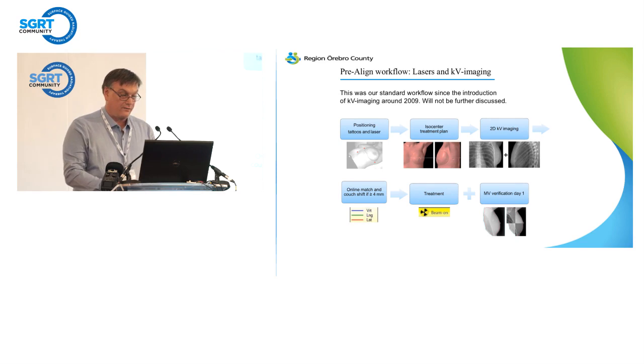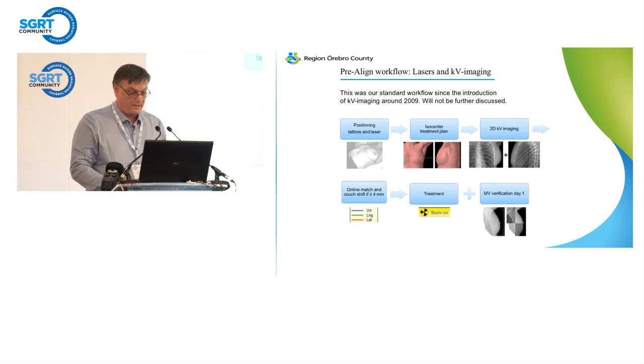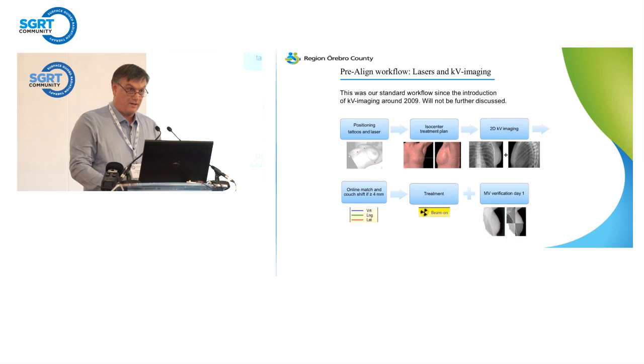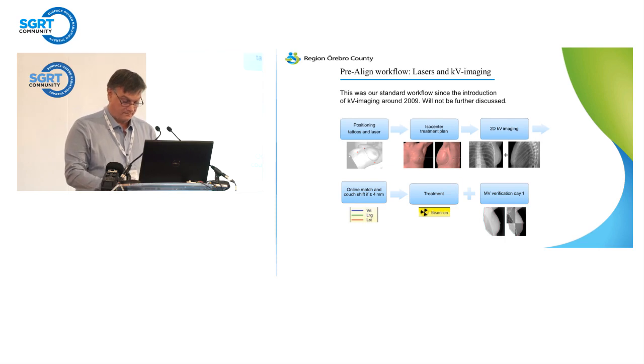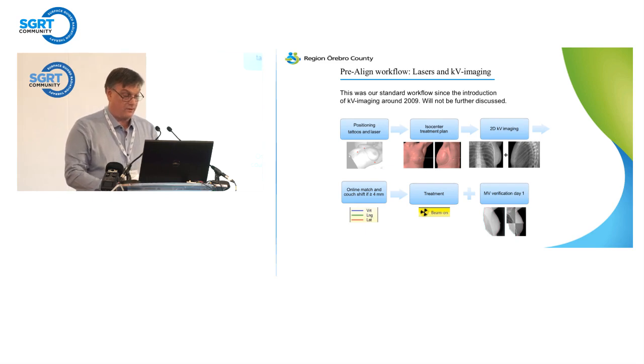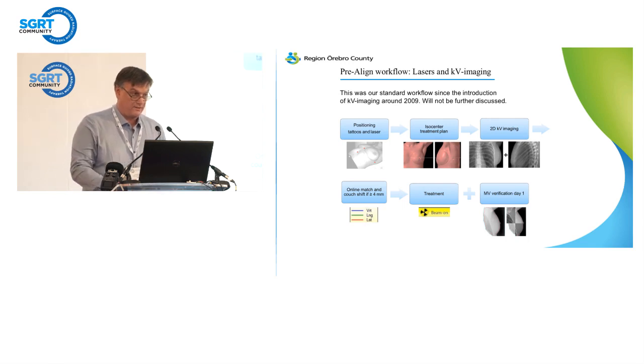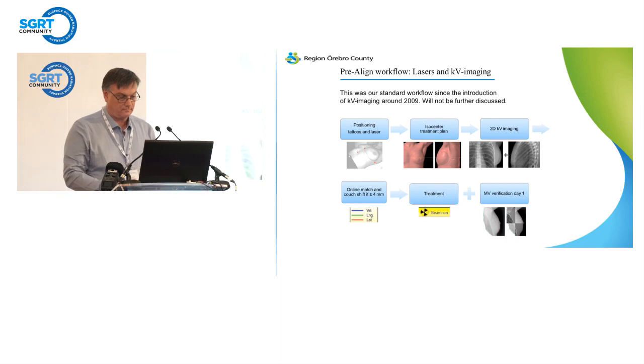This is our pre-AlignRT workflow — quite standard procedures at the time. We set patients up according to lasers, we do 2D KV imaging, we do an online match of the KV imaging, we do treatment and MV verification at the first treatment day. One thing to point out is that when we did the online match, the routine was that we only did the couch shift from the match if we had a shift larger than a certain limit, and the limit we worked with was 4mm.